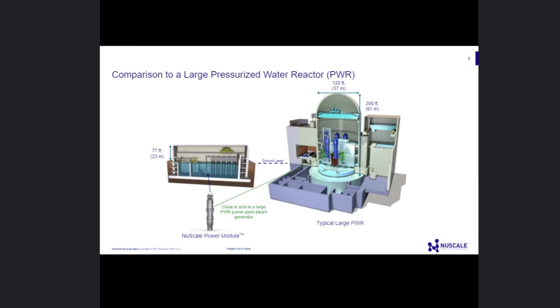Okay, we talked about how the NuScale cycle works. So again, water gets hot, goes up to the top, falls down through the steam generator where it meets the secondary water, which gets hot, goes out and makes steam. That's our regular cycle. In the event that we have to shut down the reactor, we would use, just as plants today do, the steam generators and the secondary plant to take that steam off, condense it, and pump it back in to remove heat. That's a normal way to remove heat in any plant while you have it available. That'll cool the plant down to about 250 degrees. Then you have to do something else. You have to do some kind of forced cooling.